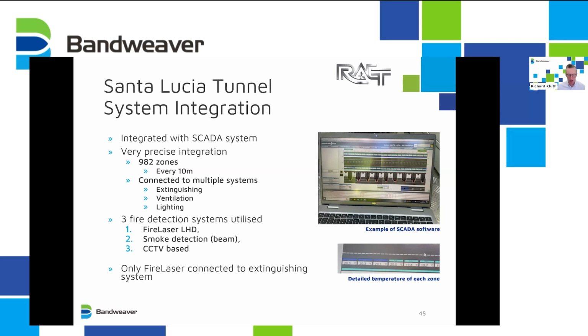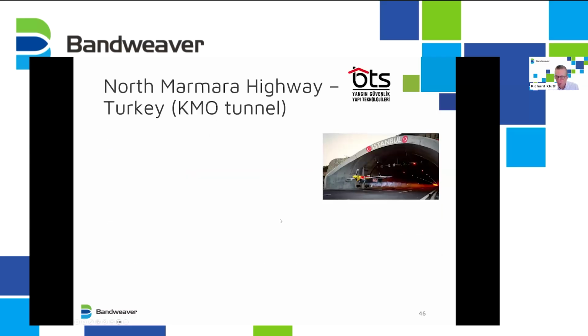So in the event any zone goes, you can have the full suppression system all focused at the point where the fire is, rather than putting it across the whole tunnel and running out much quicker, lower pressures, etc. So it's a really, really great example of how this technology is used together with the suppression system.